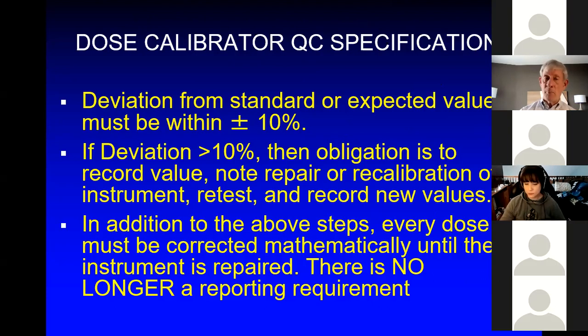We have 2 of them. We check both of them every single day. And that way, if one of ours fails, we have a backup. Now, our main calibrator is 20-something years old, and we have never had a repair to it. They are very reliable, very stable instruments, and we rely on them every single day to maintain patient safety for radiation doses.